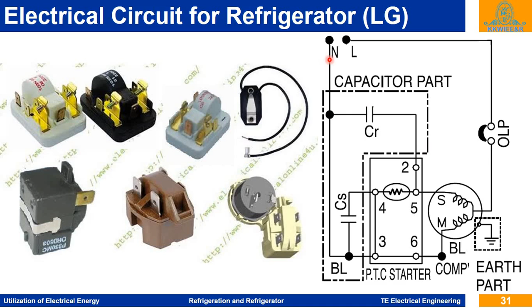Before starting the function of this PTC relay, here there is a single phase supply. The phase is connected through the overload protector to the common of the starting winding and the main winding. The main winding is connected to the PTC starter and to the neutral. The starting winding is connected through terminals 4 and 5, through the positive temperature coefficient material, through the starting capacitor, and through terminal number 2, through the running capacitor, to the neutral. Now we'll see how this PTC starter works.